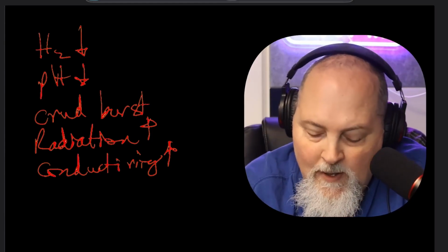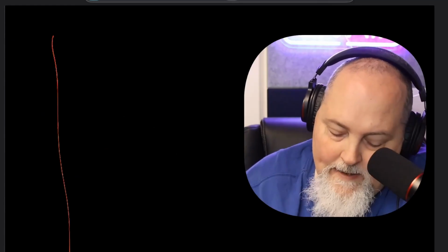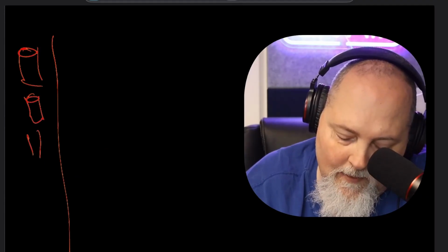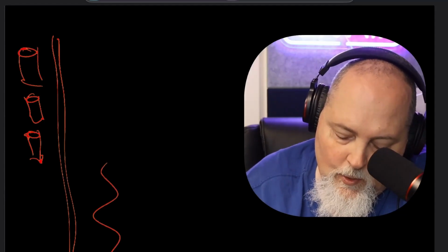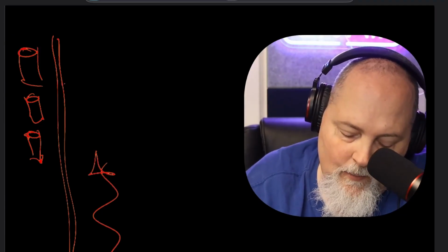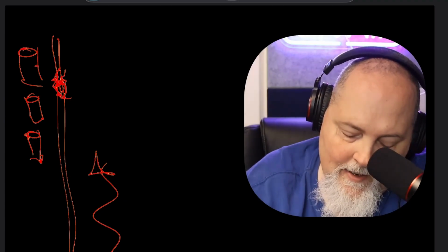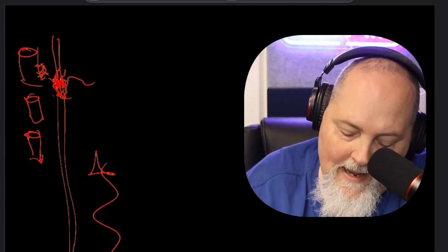So a fuel element failure is where, like we've talked about, a couple of the things that affect the cladding, affect the zircaloy. So if I've got the fuel pellets in here all stacked up, I'm just drawing them with spaces, but they're stacked up. And this is the zircaloy cladding, and then this is the coolant traveling through here. And we get some corrosion, and this blisters, bubbles, and then the corrosion starts and it eats through. And maybe this pellet here has some fission products on the side that have released into the helium inside the fuel pin, and then now it has a path to get out. So now we can leak gaseous fission products into the coolant.